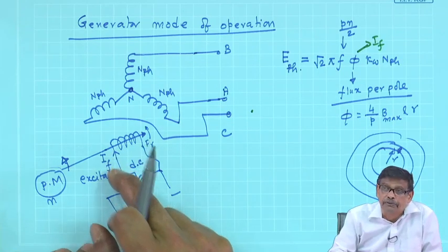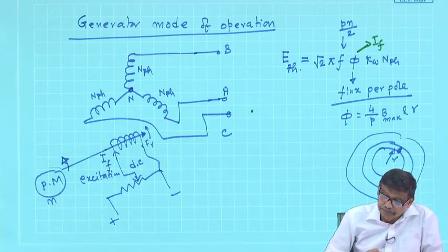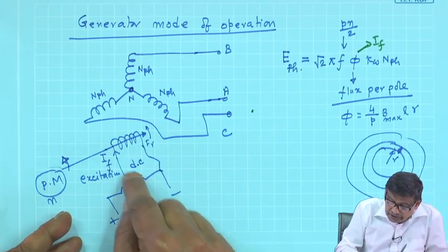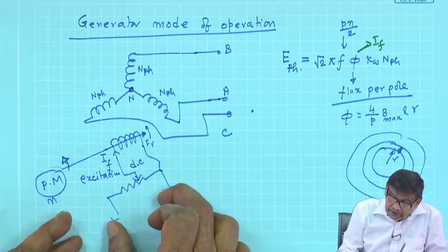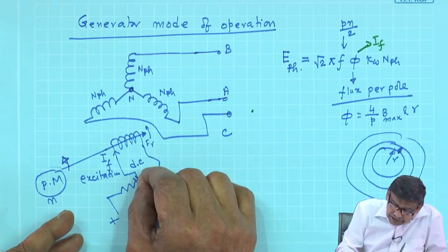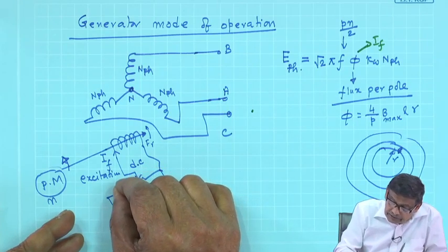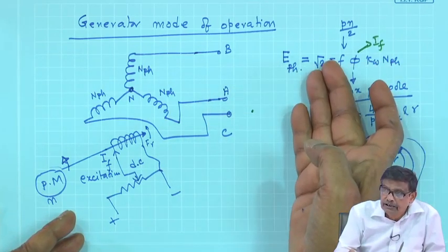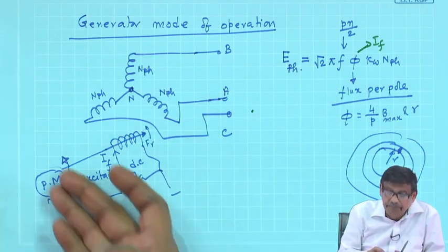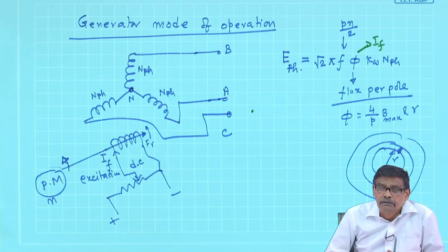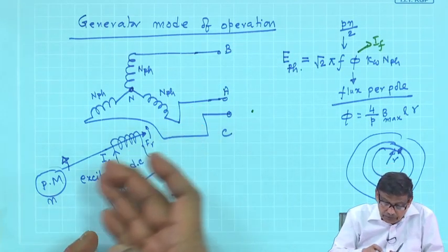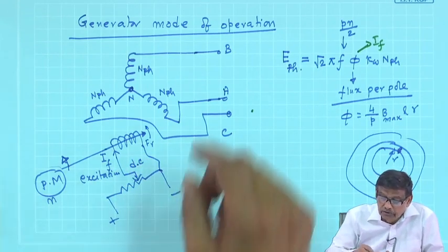If field current is zero, there will be no induced voltage. Increase the field current using a potential divider — your flux per pole increases and the induced voltage is directly proportional to it, while speed is kept constant. If you want to generate 50 Hz voltage, you must drive at the correct speed, calculated as n = 2f/P.